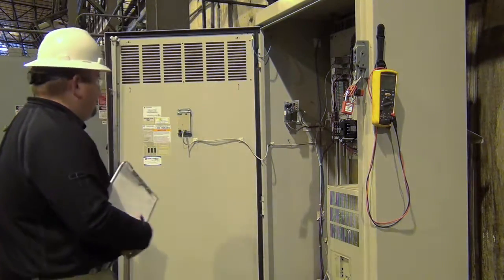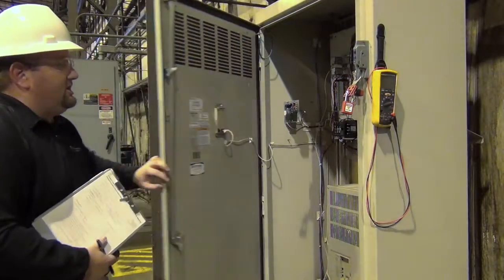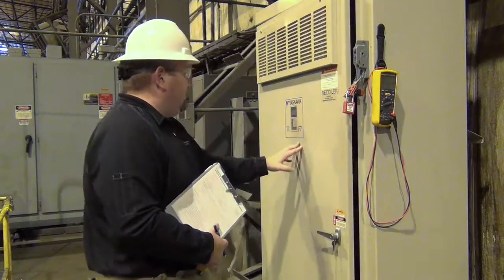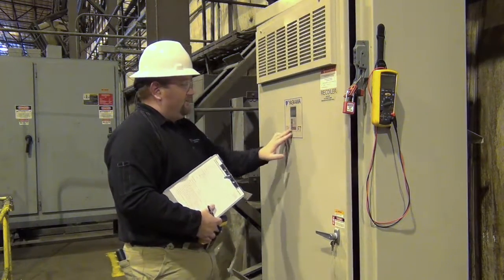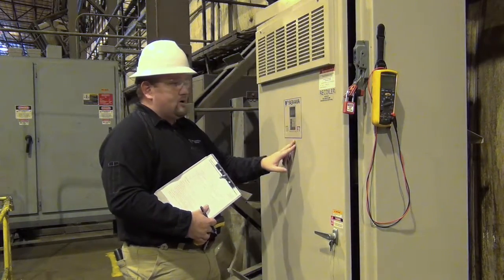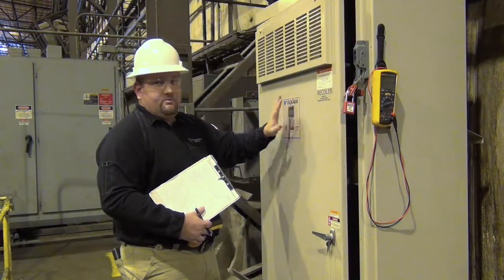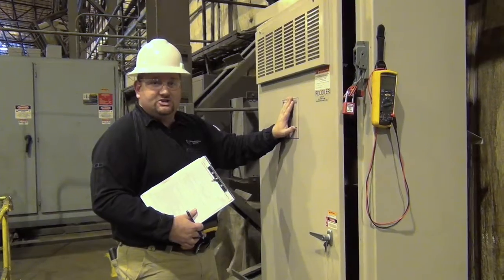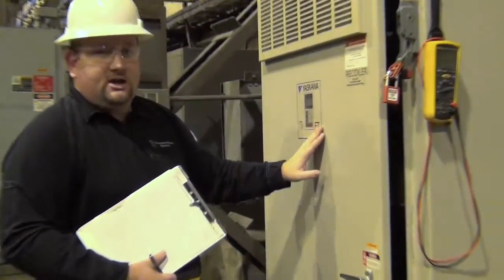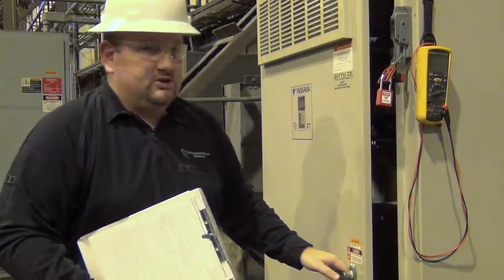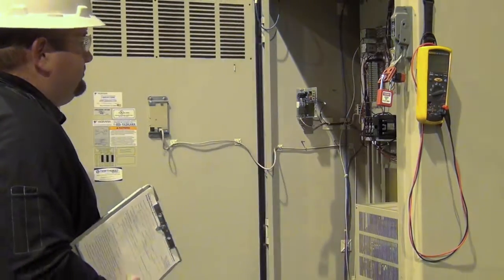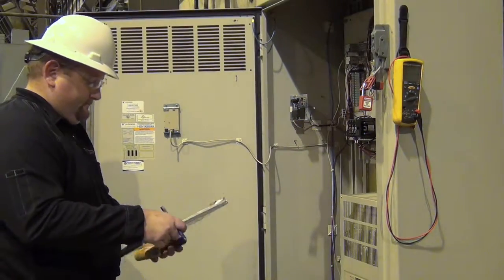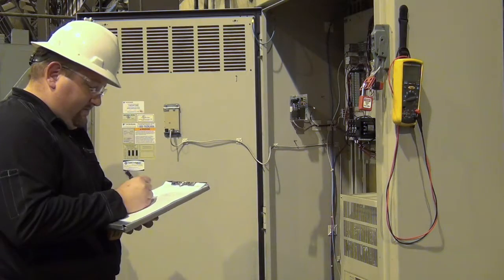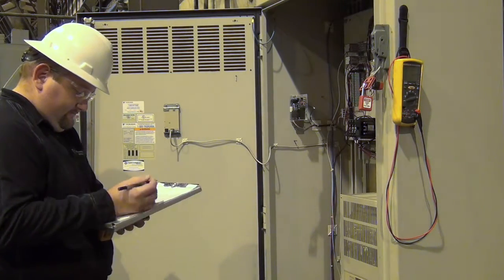We'll take a peek at the keypad of the drive. In this configuration, the keypad's on the door. Same thing. Is there any damage to the overlay? Do any of the buttons look excessively warm? Once we're done, we'll power it up and verify that all of the digits and the buttons are actually properly working. But for now, we'll just give it a visual inspection. And the keypad condition appeared good.